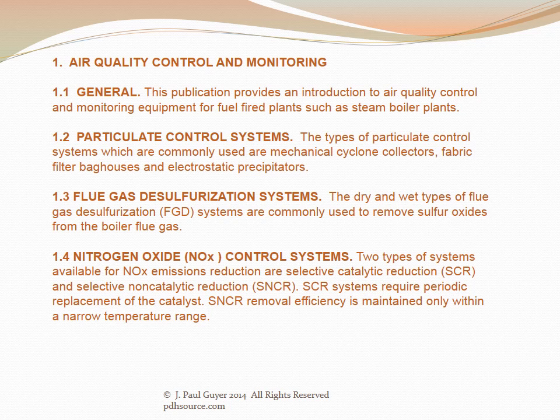The types of particulate control systems which are commonly used are mechanical cyclone collectors, fabric filter bag houses, and electrostatic precipitators. The dry and wet methods of flue gas desulfurization, abbreviated FGD — a heads up that due to the complexity of the terminology, many abbreviations are used. FGD systems are commonly used to remove sulfur oxides from the boiler flue gas.